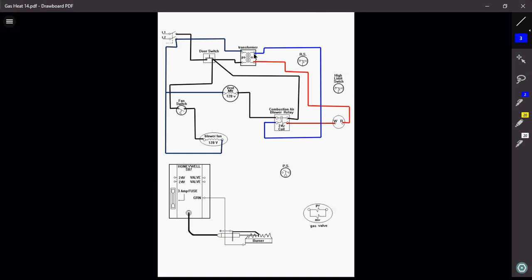Usually, 95% of the time, the red wire that's coming off of your transformer, that's your 24 volt power, and that's usually going straight up to the thermostat upstairs in the home. Okay, so that's one circuit there. Again, source, path, switch, load, right? The 24 volt side, my secondary, that's my source. Here's my path. The thermostat is my switch. The coil is my load. And I am coming right back up to my secondary side of my transformer.